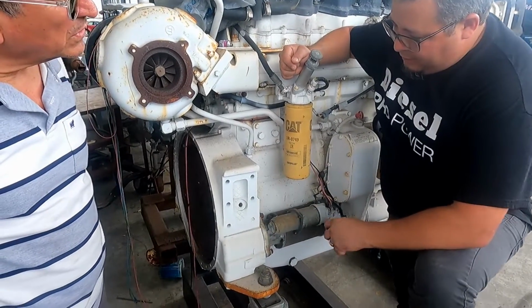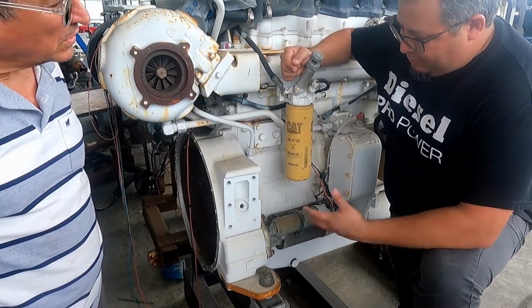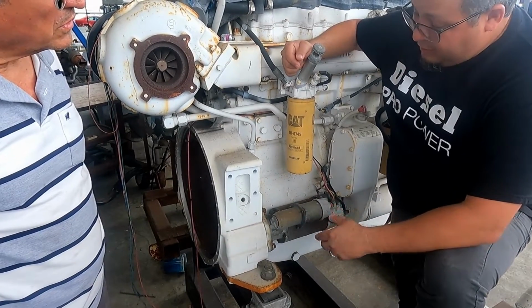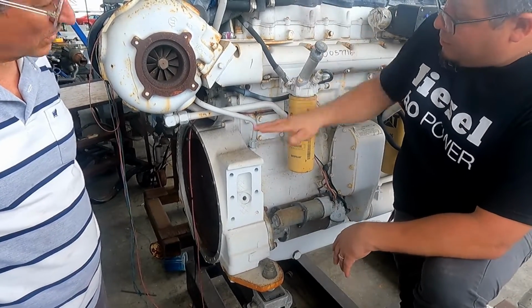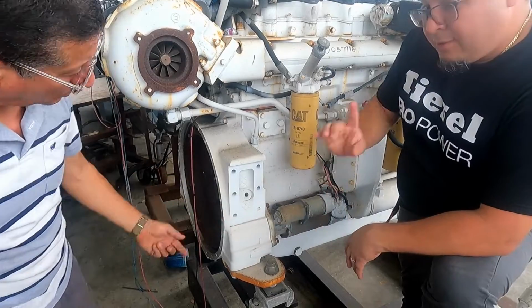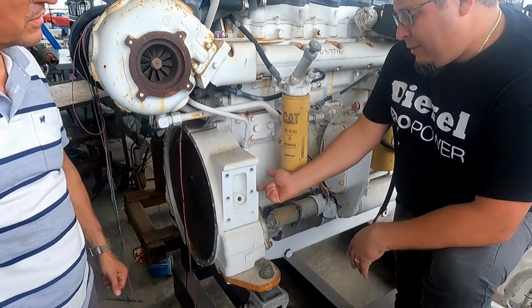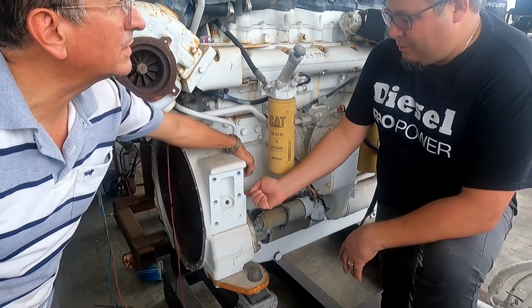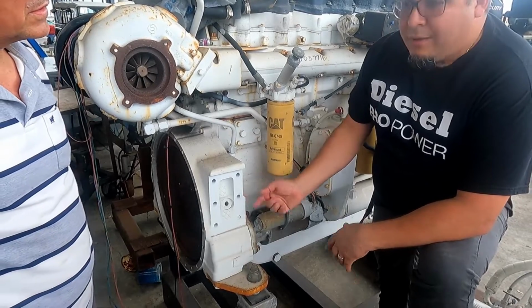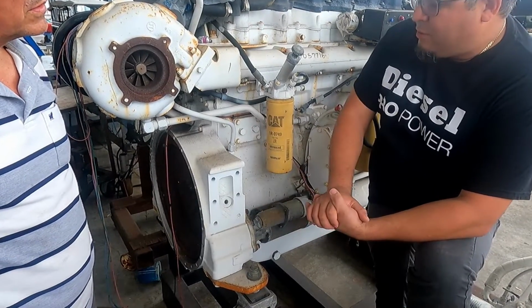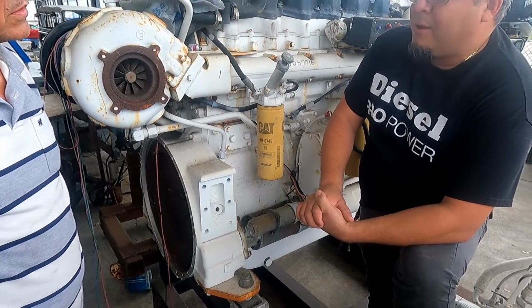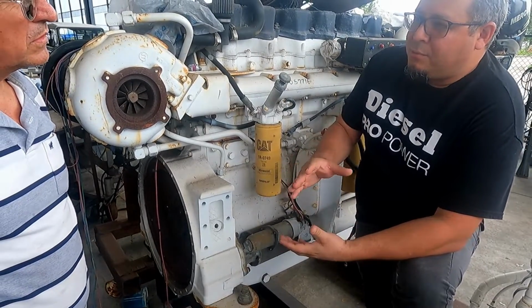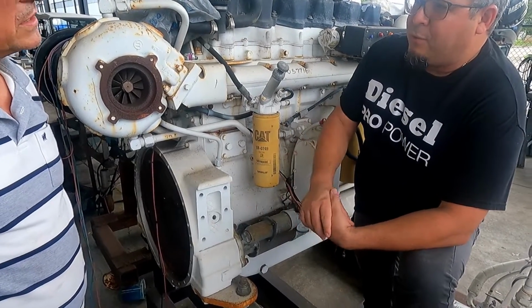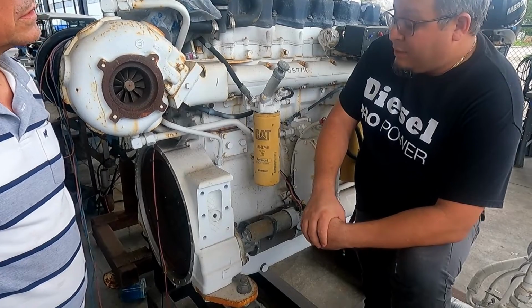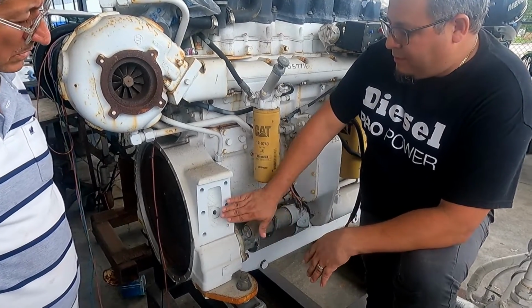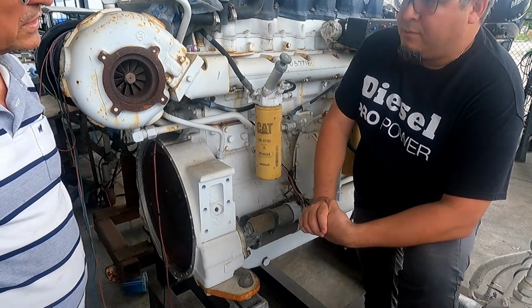The magnetic pickup position can vary in different places. It could be on top of the flywheel, on the side, or sometimes on the back, lateral to the flywheel housing. It can also be found on the bottom, but that's not recommended. Factories stopped manufacturing that way because it was a dangerous position — it could break often when moving or installing the engine. So the main reason is to place it where it can be kept safe.